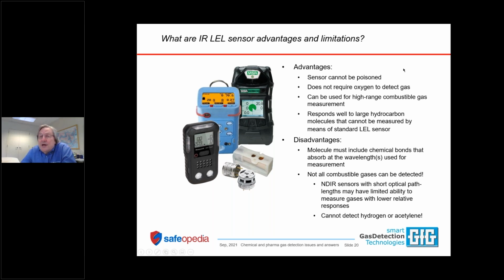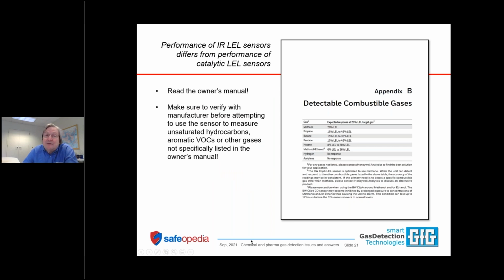But when it comes to IR-LEL sensors, they can't be poisoned. They don't require oxygen. They can be used for high-range measurement, and they respond very well to very large molecules that cannot be measured easily by means of a standard sensor. The disadvantages: the molecule has to include chemical bonds that absorb at the wavelengths used for the measurement. If you don't have absorption of infrared light at those wavelengths, then the gases are invisible. So not all combustible gases can be detected, and you can't detect hydrogen or acetylene ever.